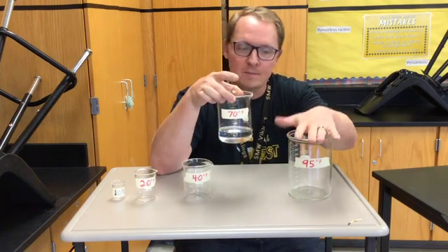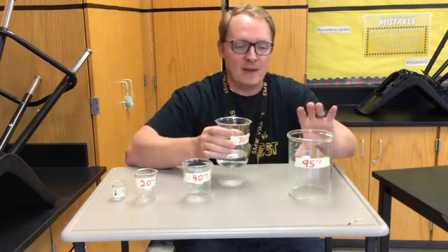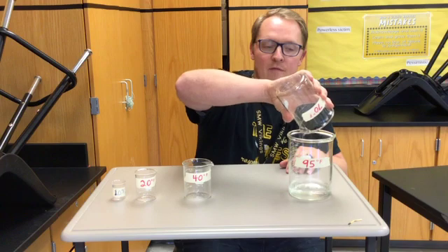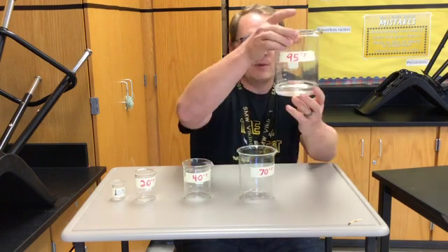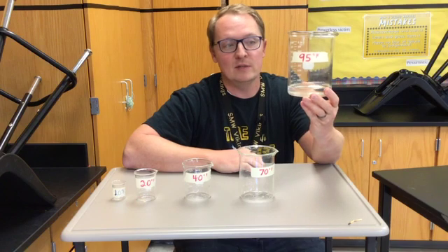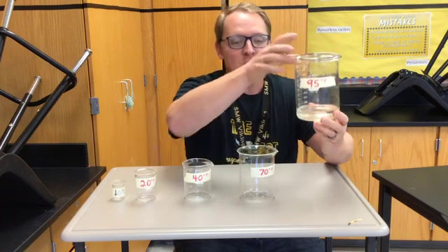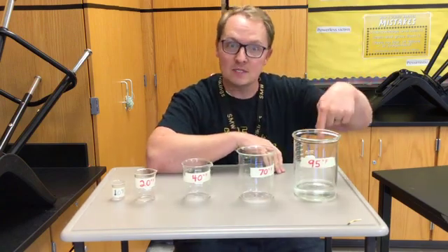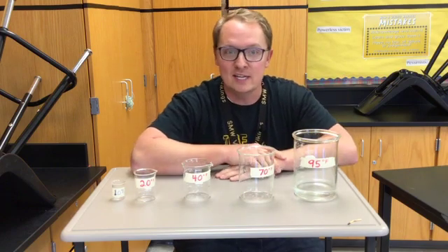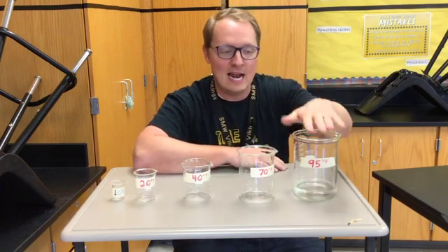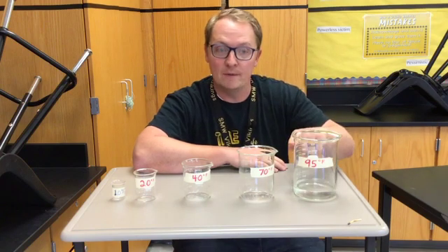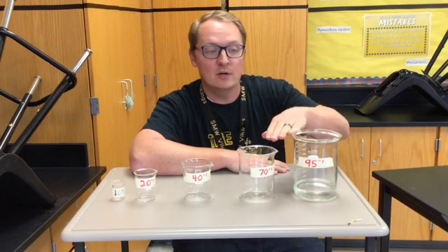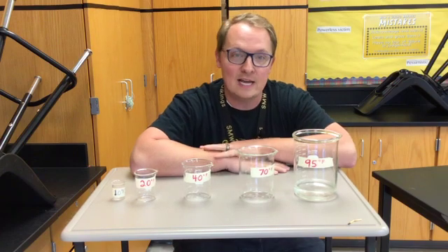What if the air continues to warm? If the air jumps up to 95 degrees, the capacity of that air to hold moisture greatly increases. But if we have the same amount of water vapor, look at this. This is probably down somewhere around maybe 10% relative humidity, maybe 12 or 13, right? So as the air warms up, what normally happens is relative humidity drops, because that's what we chose to use in the United States. It's a percentage of how much moisture is in the air compared to how much it could actually hold. The only way to get to 100% relative humidity is to have the air at that temperature absolutely brimming or completely saturated with moisture.